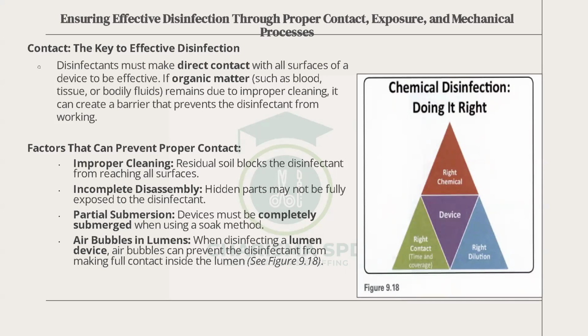Factors: improper handling. You must make sure that you handle instruments properly. Improper cleaning. Now, soil blocks. If it's not clean, it cannot be HLD. It cannot be sterilized. So cleaning is very key, paramount. Incomplete disassembly. If the instrument has to be disassembled, the flushing ports. By flushing ports, I'm referring to these scopes because some have the flushing ports, etc., and then the irrigation channel, etc. If those things, those buttons are not removed, then there is a problem. You must fully disassemble.